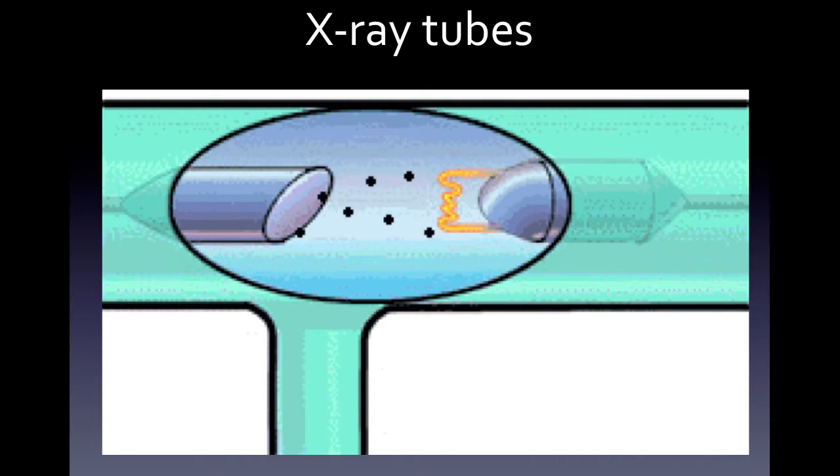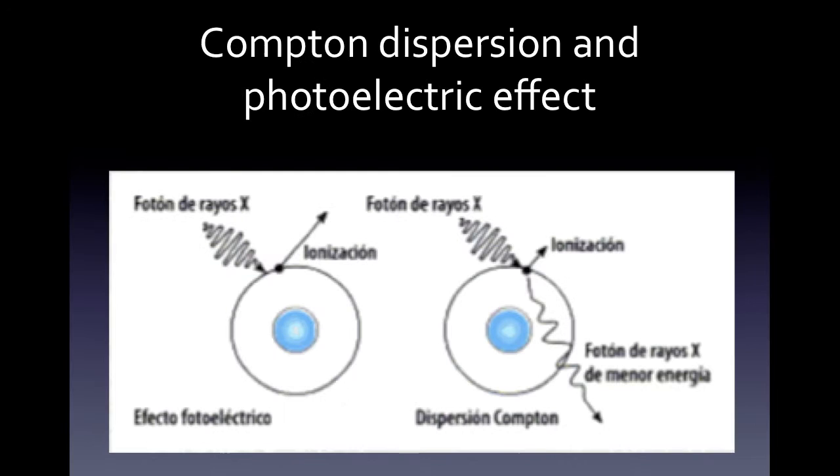X-ray tubes are without air and consist of two parts. The cathode is made of tungsten filaments, and the anode is a plate which turns the electrons into photons. To prevent wear and tear, it spins so that the electrons do not strike at the same point. The anode may be made of tungsten, molybdenum for mammography.